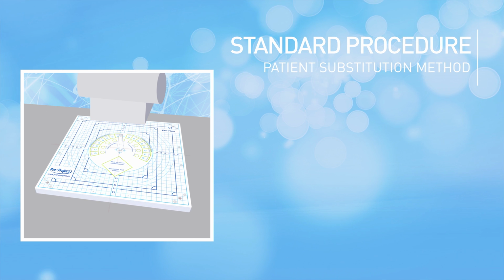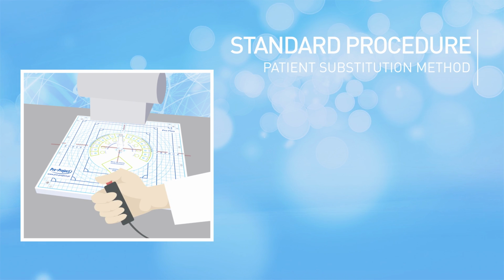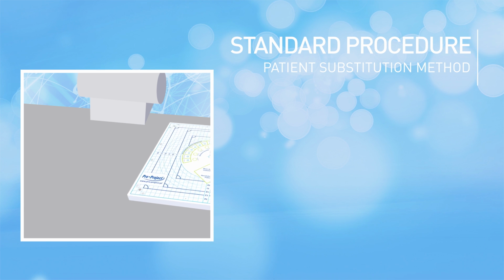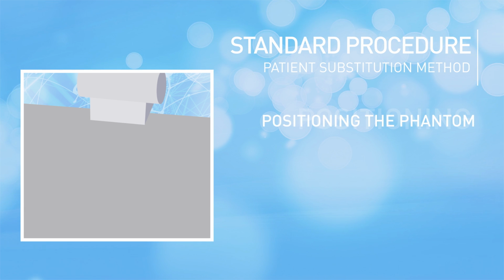In short, the quality control process comes down to the patient substitution method, where you treat a phantom as you would your patient. You start by positioning the phantom in the device.